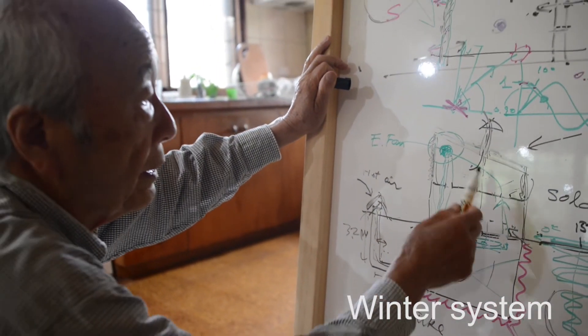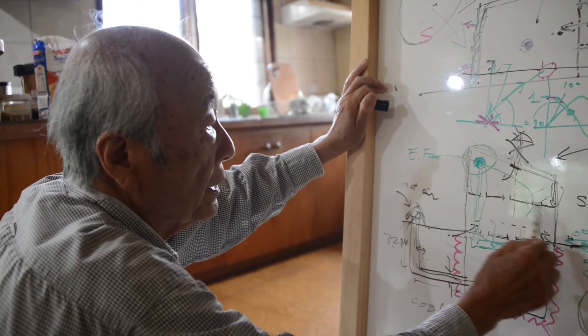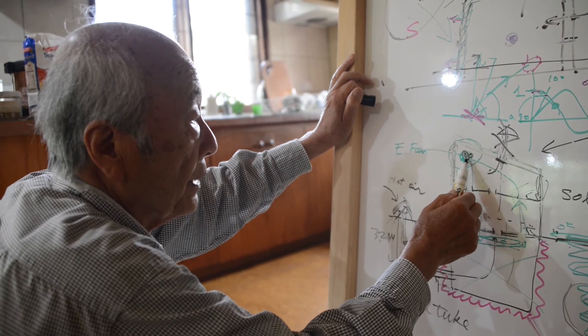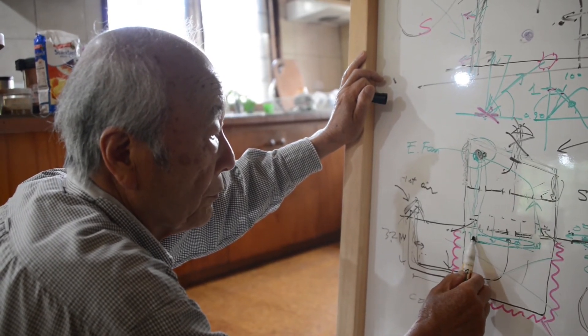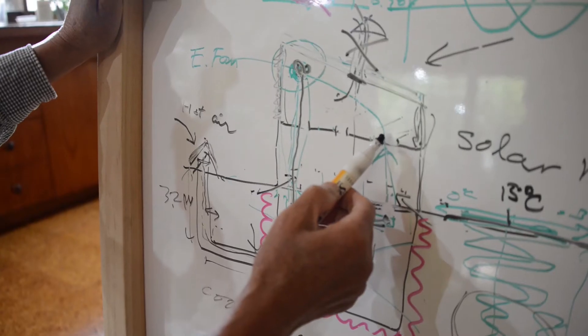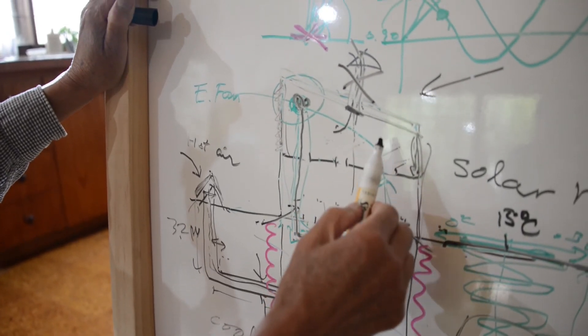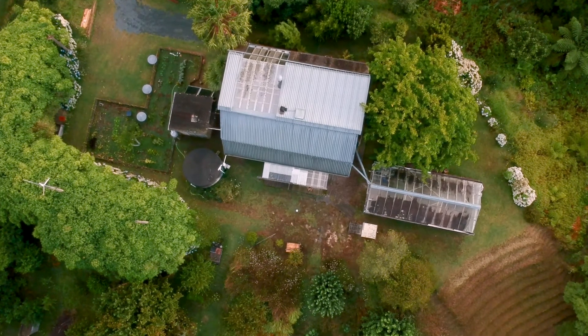In the winter, I close the bottom opening. The solar room gets heated up. The highest spot in the solar room is here, so I put an electrical fan at the top of this air duct, which runs from there to beneath the ground floor and is distributed through six branches. It comes back to the solar room and is again heated up by the sun. Going down and going up cancels the pressure — only the resistance loss is supplied by the electrical fan, so not much power consumption.